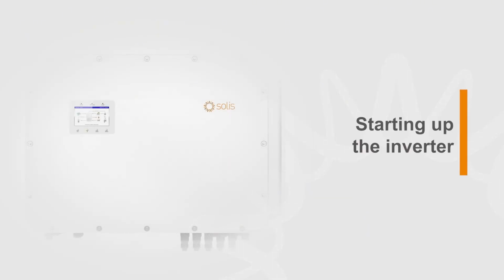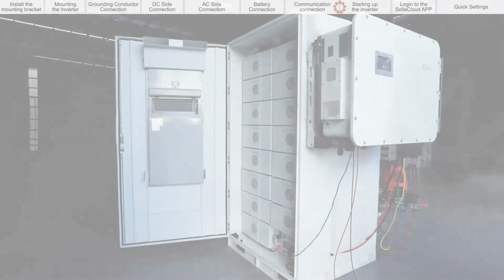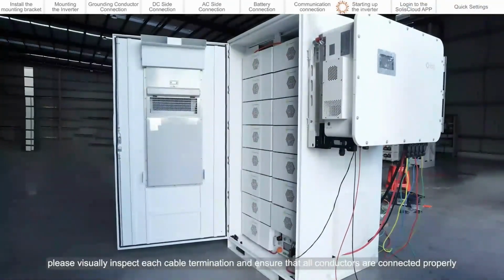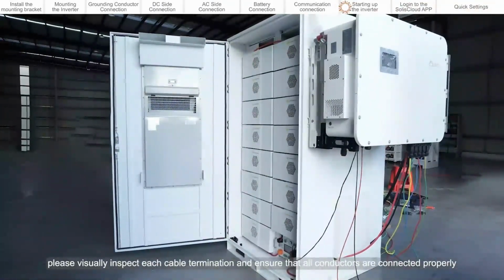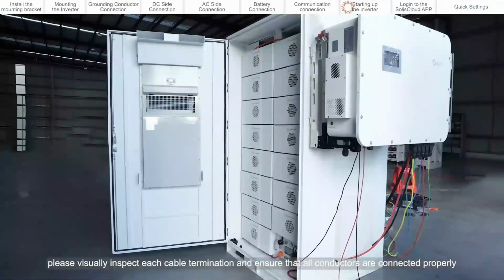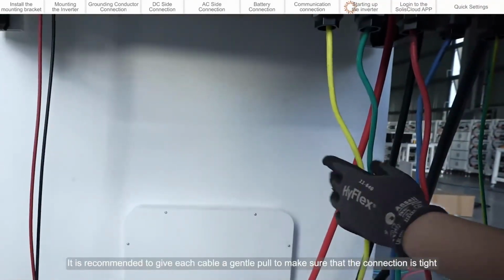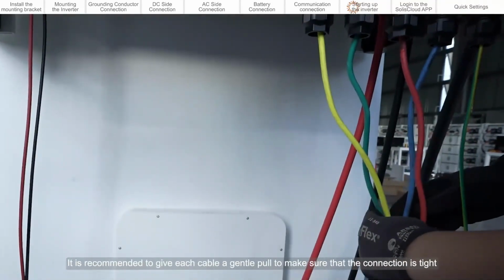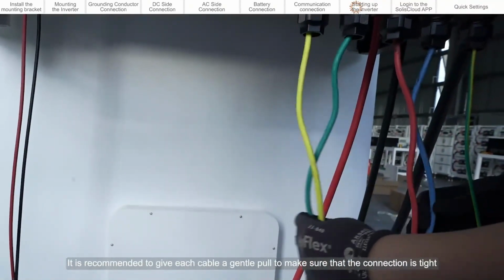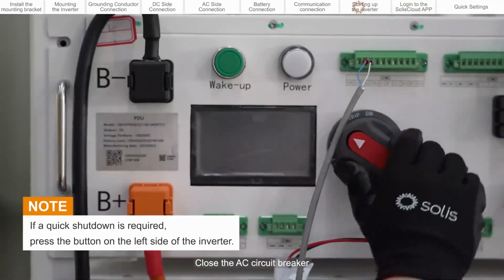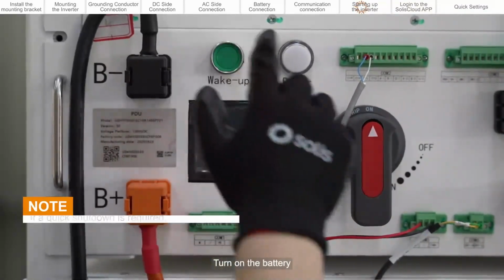Starting up the inverter. First, please visually inspect each cable termination and ensure that all conductors are connected properly. It is recommended to give each cable a gentle pull to make sure that the connection is tight. Close the AC circuit breaker. Turn on the battery.